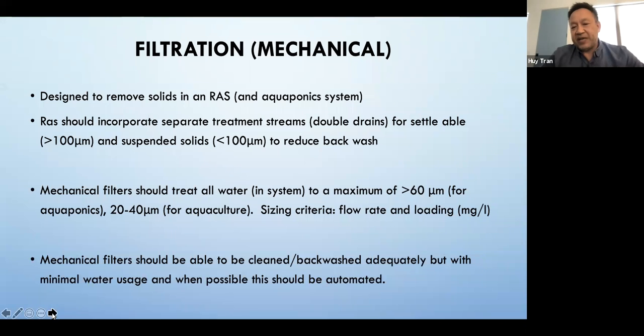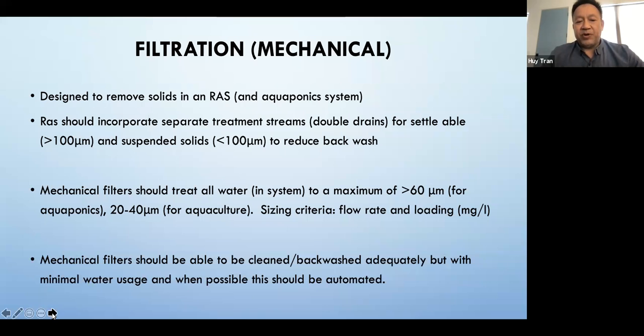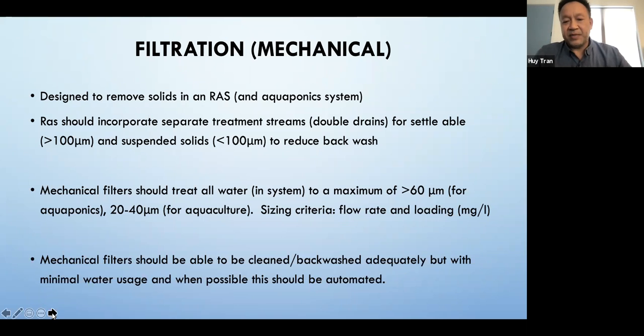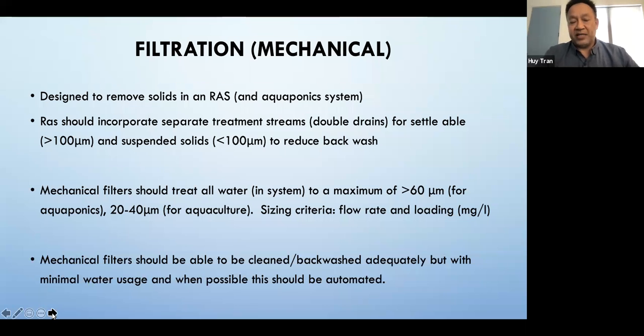Mechanical filtration is designed to remove solids in a recirculating aquaculture system. RAS really should incorporate a separate treatment stream — a double drain for settleable solids greater than 100 microns, which helps reduce backwashing. Mechanical filters should treat all water; there shouldn't be any side stream bypassing mechanical filtration. All water recirculating in your system should go through some type of mechanical filtration.